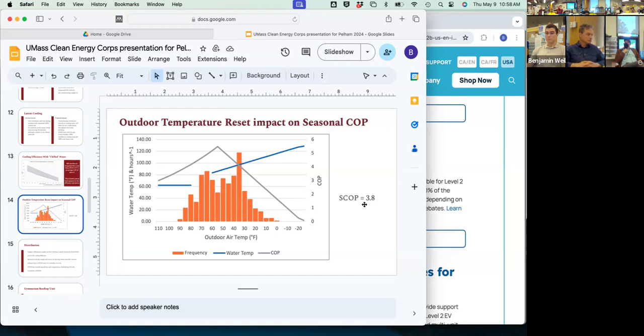The unit ventilators have sort of so-so filters in them, average for the period. Since they don't need to move as much air or temperature, is it worth thinking about increasing the filtration so that on the room by room level, we also are pulling more dust and whatnot out of the air? Exactly. So there's trade-offs, and you could judge these in real time, you could actually experiment, right? If we increase the resistance of the filter, right? Right now you've got, say, a MERV 8 filter, right? It doesn't have a lot of resistance, and that's important because the fans need to move a lot of air. You increase the resistance of the filter, you're moving less air.